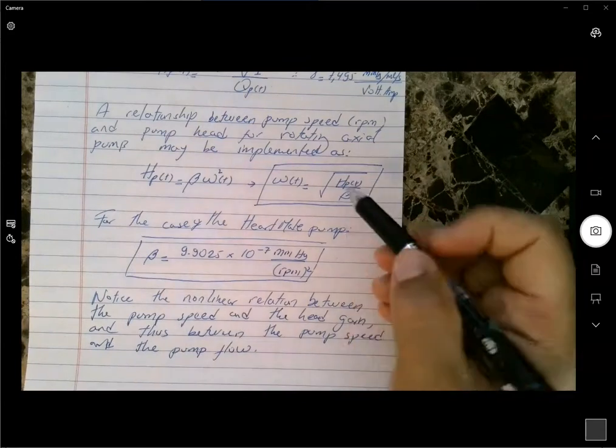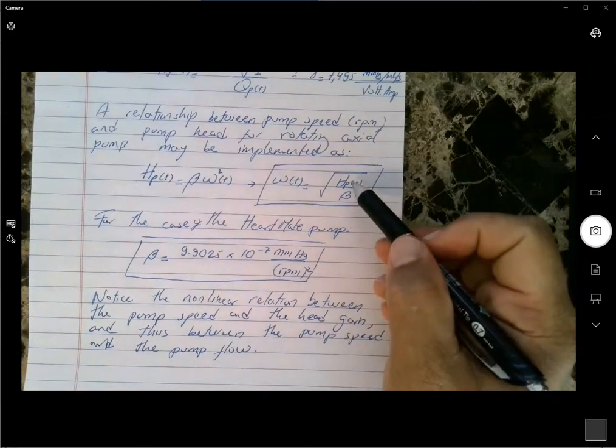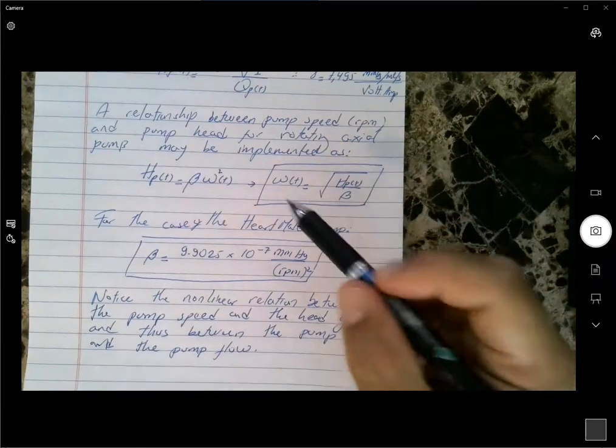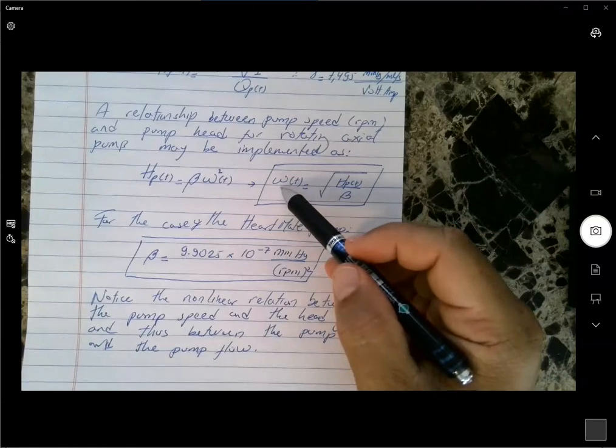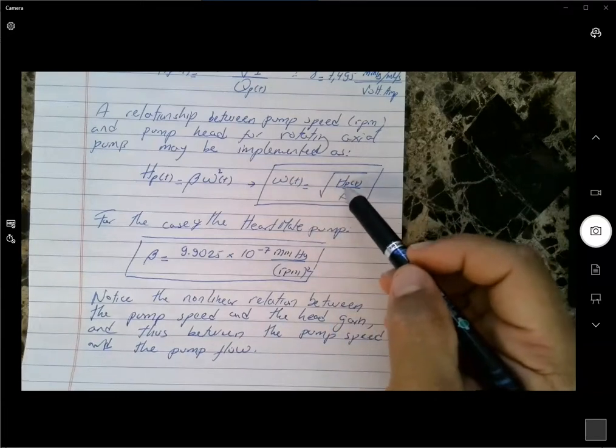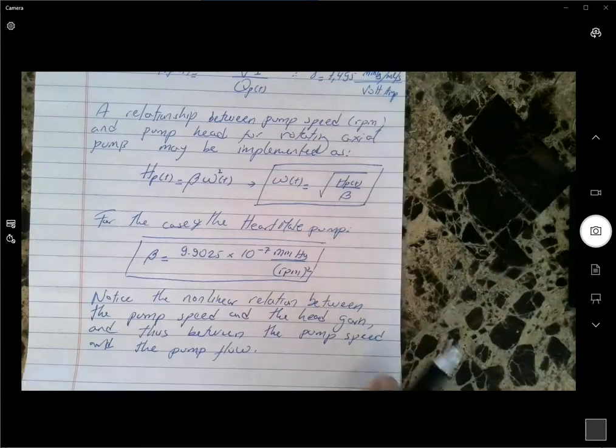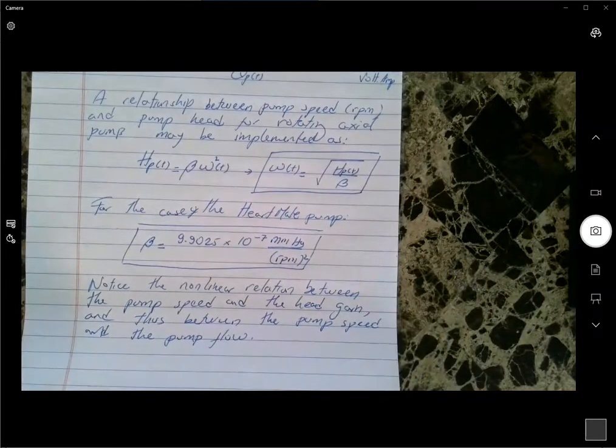Remember that the HP is related to the inverse of the pump flow, and therefore omega, which is the rotating speed, RPM, is related to the square root of the inverse of the pump flow. So we have a whole set of nonlinear relationships here that would make a control system ever more unstable and difficult to control.